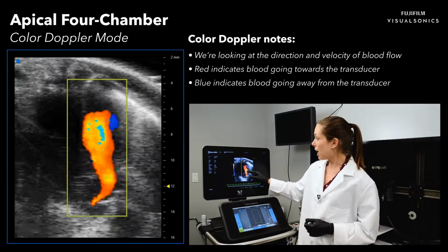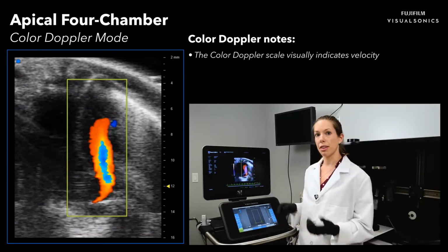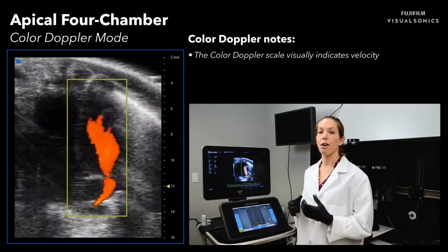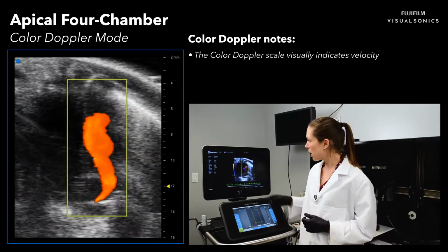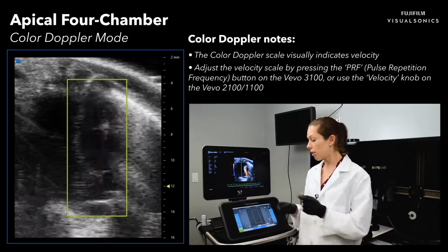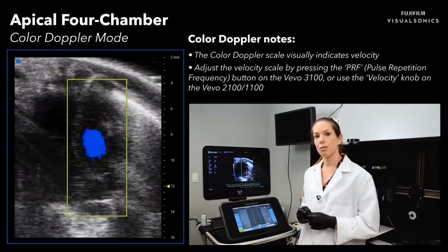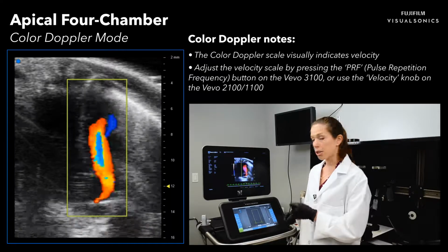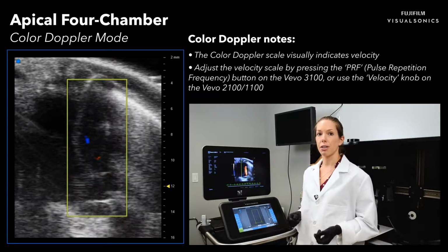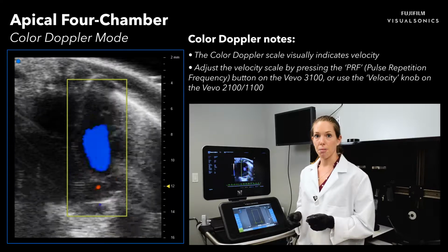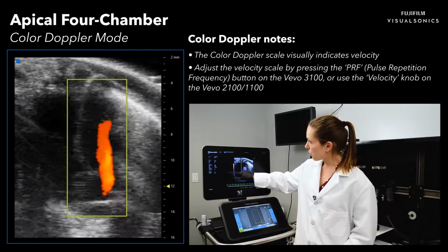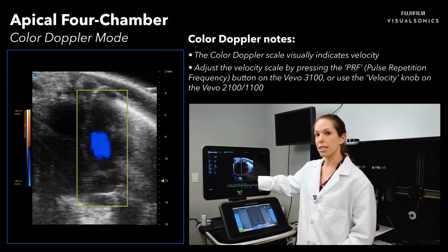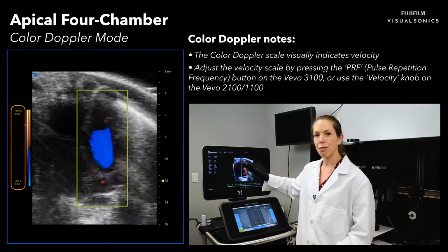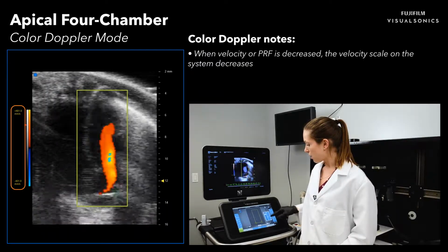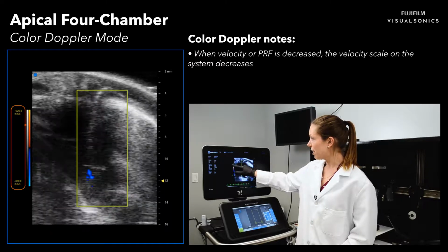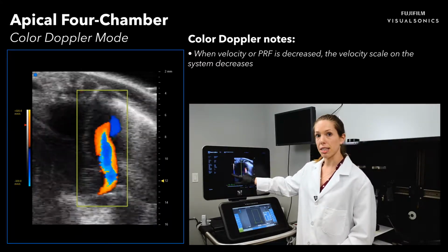We're also looking at velocity, so how red or how blue that signal is indicative of how fast that blood is moving. And we can adjust that velocity. On the 3100, we use pulse repetition frequency, or PRF, to adjust the velocity. On the 2100 and 1100, we use simply the velocity knob to adjust the velocity. On the screen here, you can see that the upper and lower limits of my color Doppler are about 400 millimeters per second. If I turn the velocity or the PRF down, then I decrease that color velocity scale.